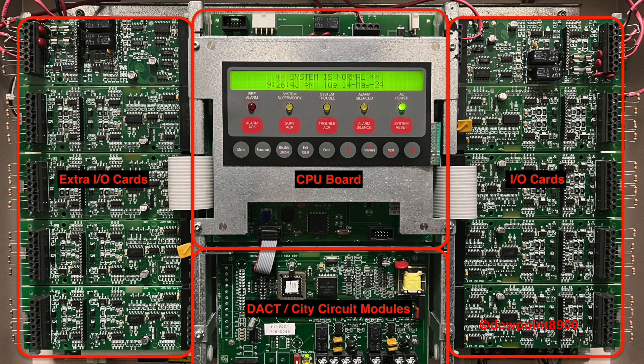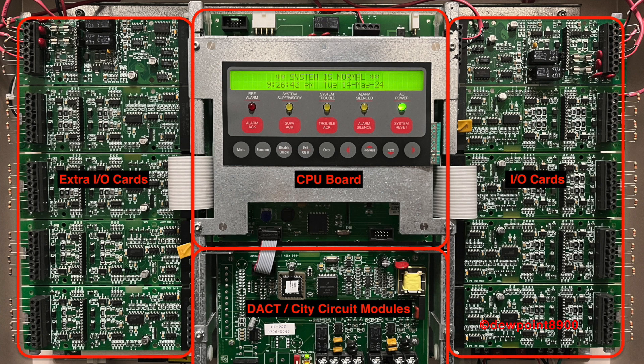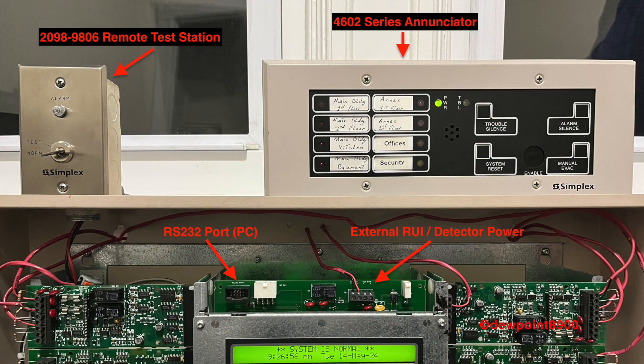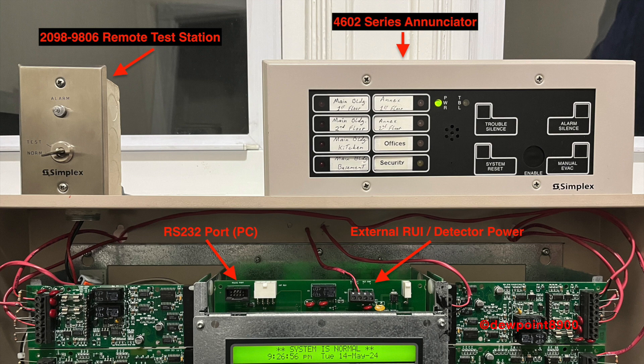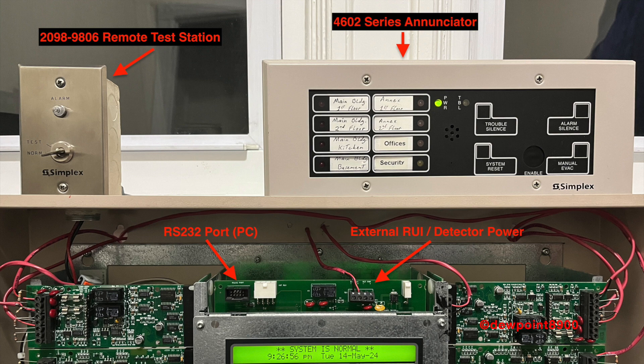At the center of the back box is the CPU board. This is where the panel's configuration is stored, along with the keypad and LCD screen. At the top left is an RS-232 port for a PC connection. The PC interface mimics the keypad and LCD screen. There are terminals for the external RUI or remote user interface and resettable power for four-wire detectors. Serial annunciators like the 4602 series will connect to the CPU via the RUI terminals.